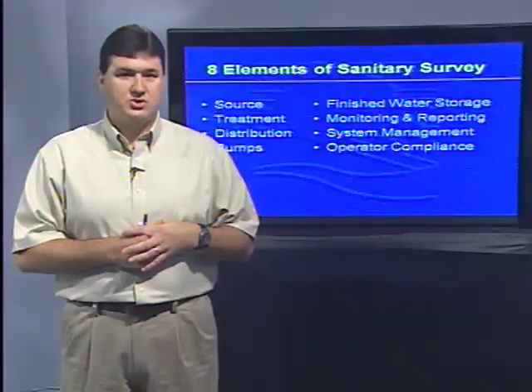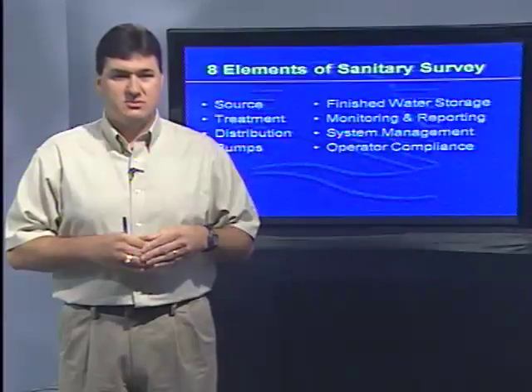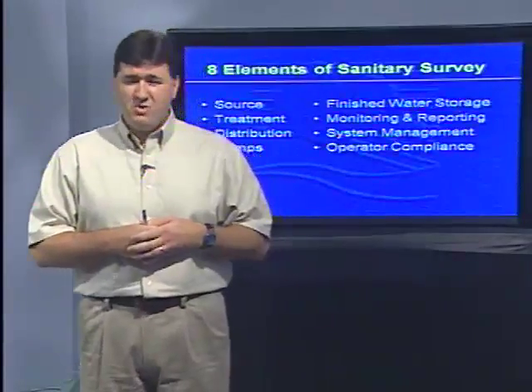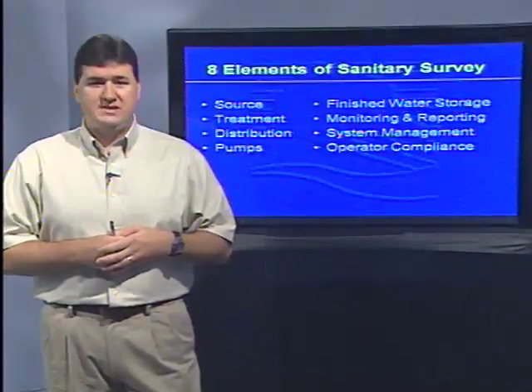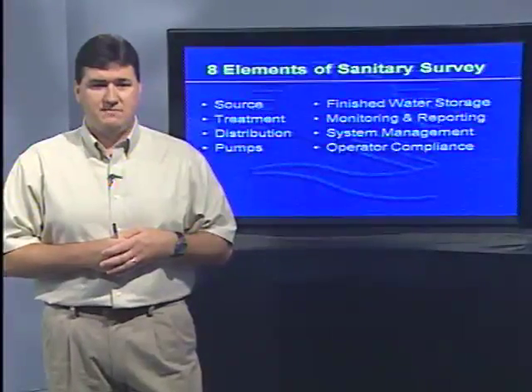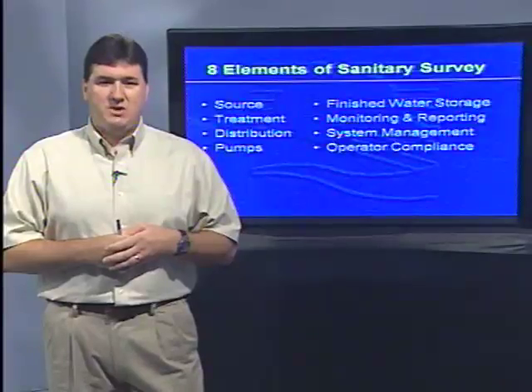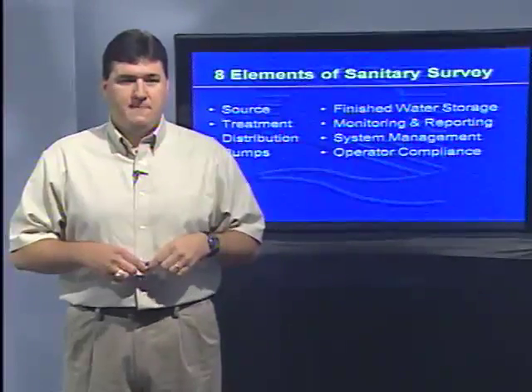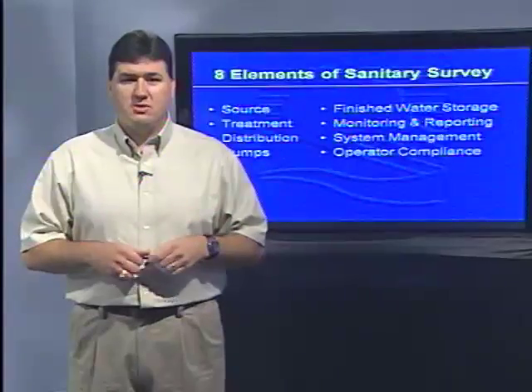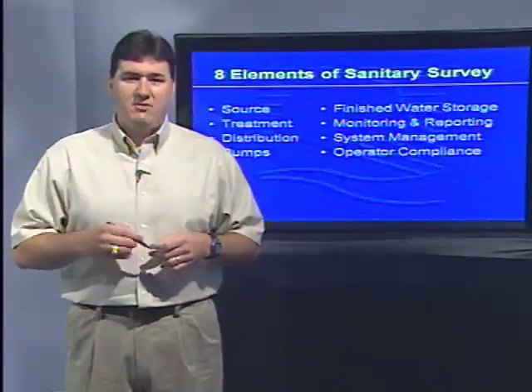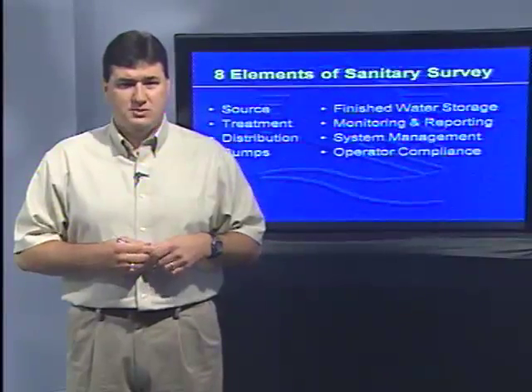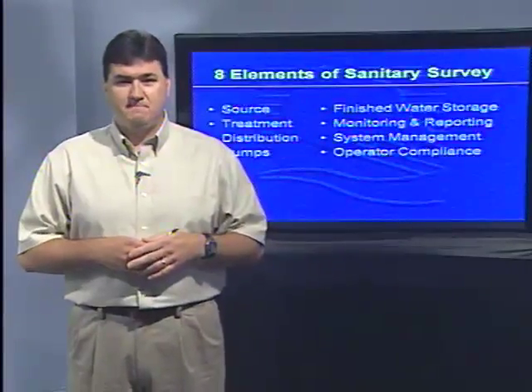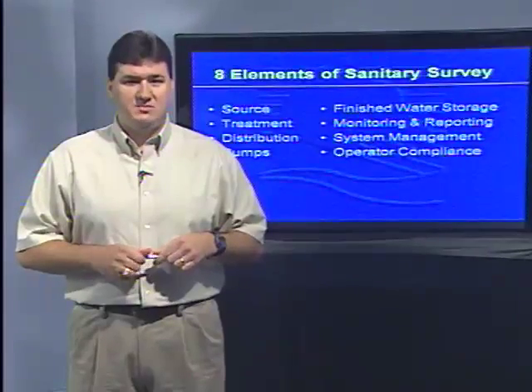We'll look at your finished water storage tanks — do they meet AWWA standards, is the roof hatch locked, is the overflow sufficient? Monitoring and reporting — we'll ensure you're taking and reporting routine samples. System management — we'll make sure you're maintaining the proper records required by the groundwater rule. Operator compliance — we'll make sure you have the operators needed, the level of certification required, and that those operators spend enough time in your facility, all in accordance with 30 TAC subchapter D.